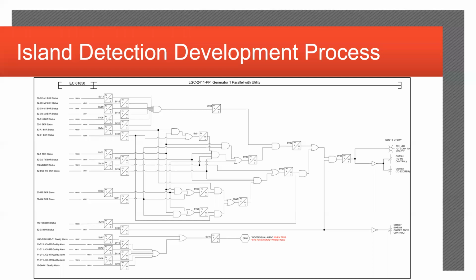One other thing to note: there were a total of 17 circuit breakers in this system that we were monitoring. And if you do the calculation, it comes out to something slightly over 131,000 different logical conclusions that you could get with 17 different binary variables. Of course, there's only a small handful of those logic conclusions that result in any meaningful value. In other words, is generator number 1 in parallel with the utility or in parallel with another generator, that sort of thing.